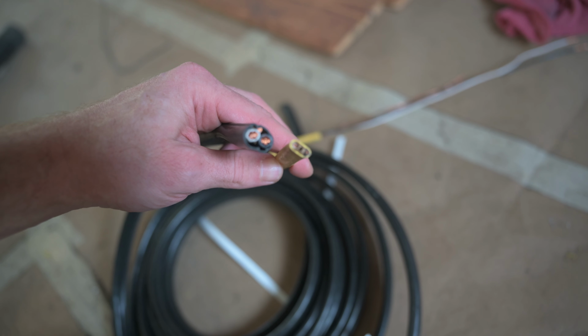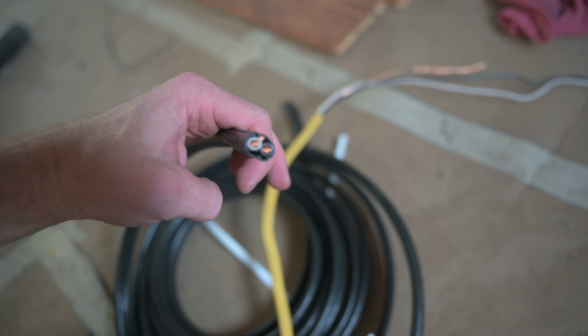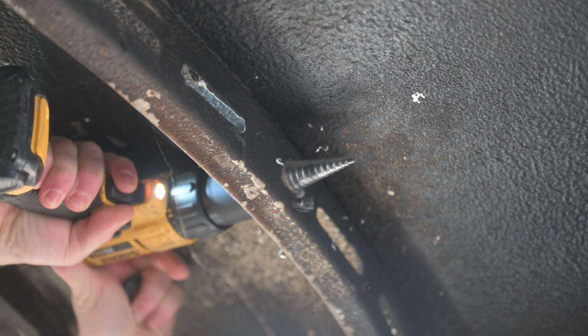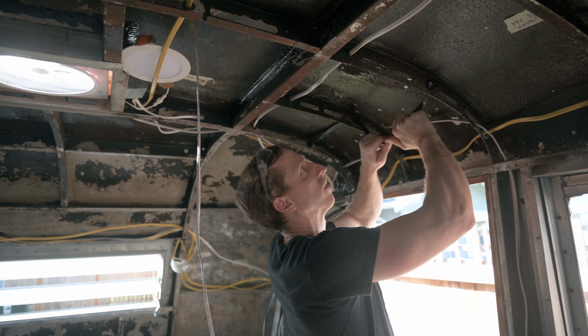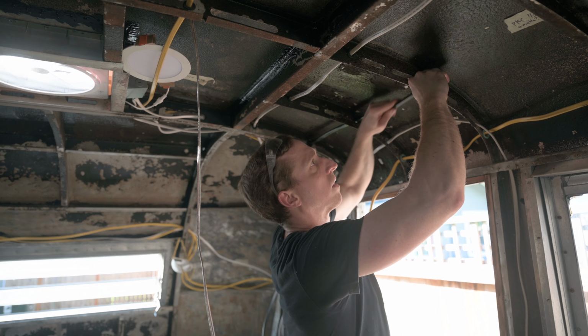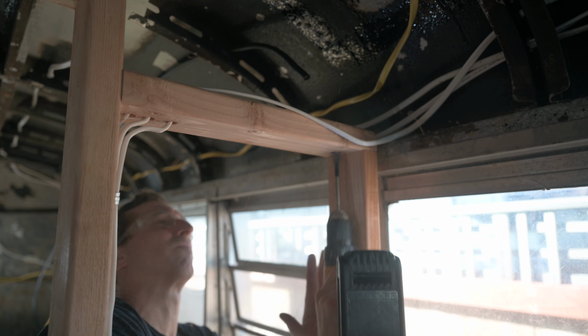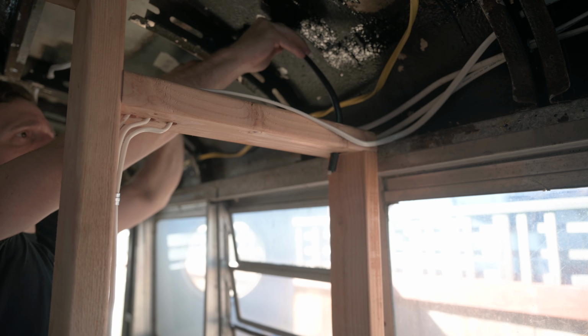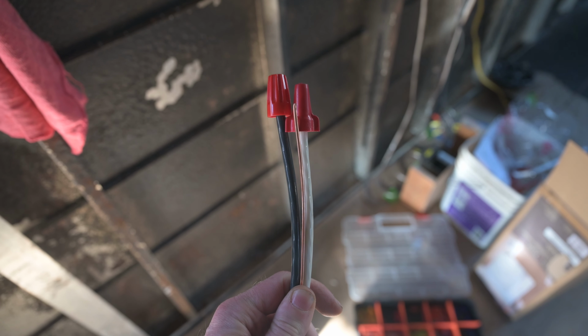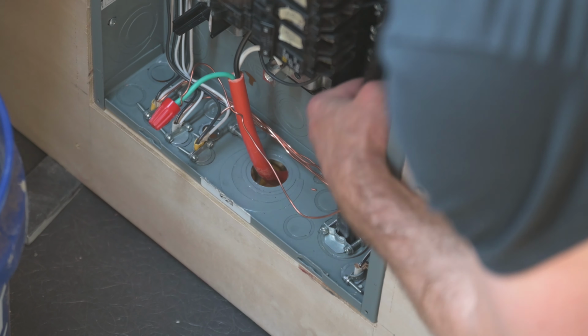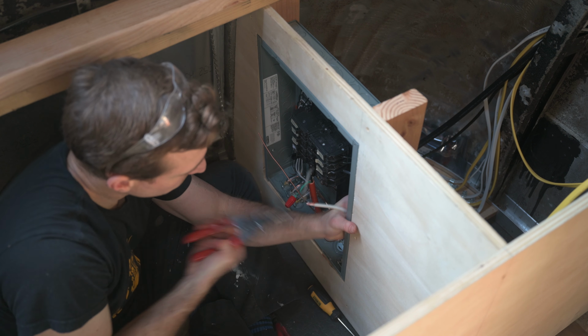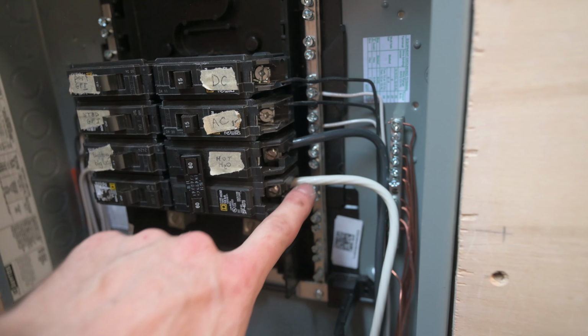And here's the difference between a 20 and a 60 amp cable. This 6-gauge cable required bigger holes, bigger grommets, and was harder to pull through the frames. Brought it to the bathroom wall where the heater will be installed. Make sure to cap those wires. And left plenty of extra length. And then it needed a bigger strain relief clamp before being connected to the 60 amp breaker in the panel.